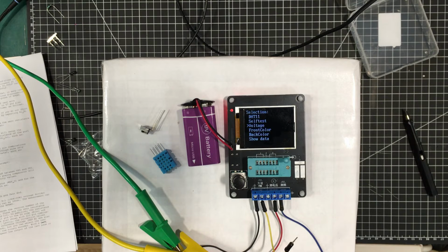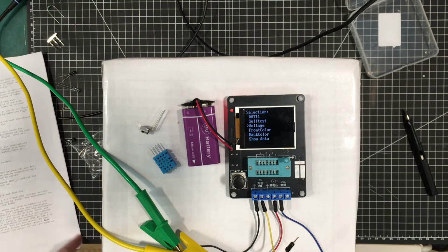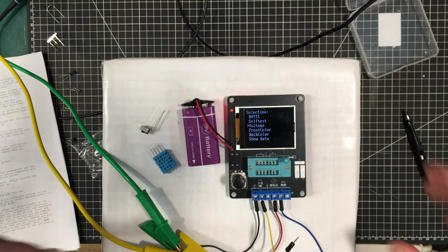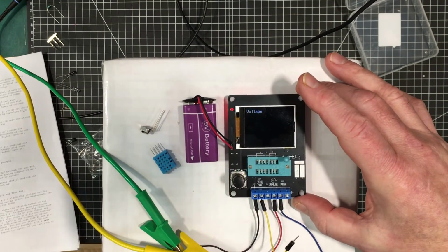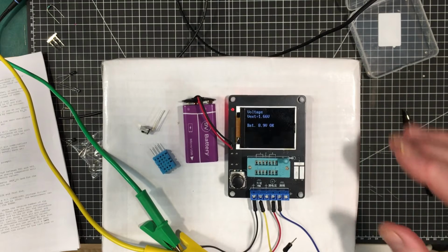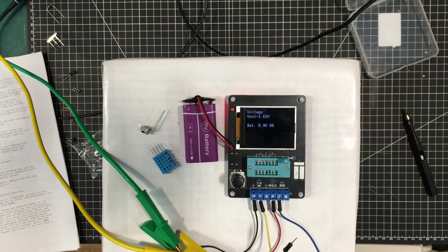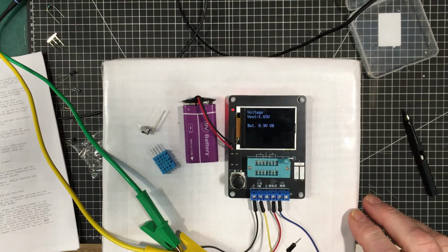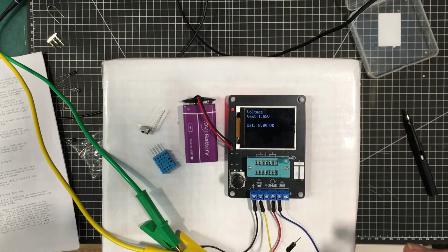Okay, so we're on the voltage here. I should be able to read a maximum external voltage of up to 50 volts DC. So let's see what we get. Got a voltage here. And we got 1.66 volts. Fluke is telling me it's 1.68 volts. So that is pretty good.